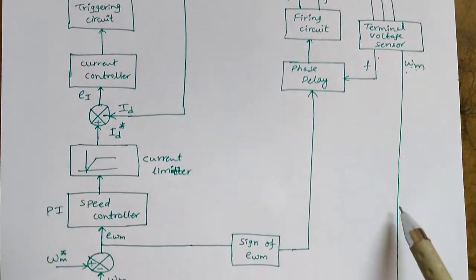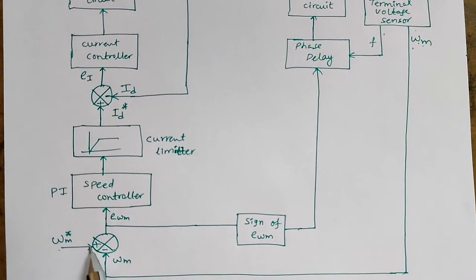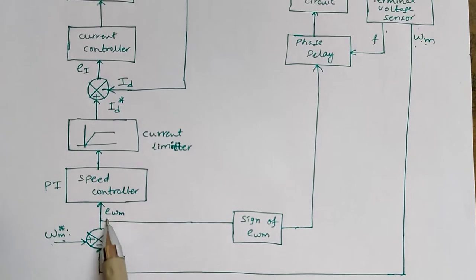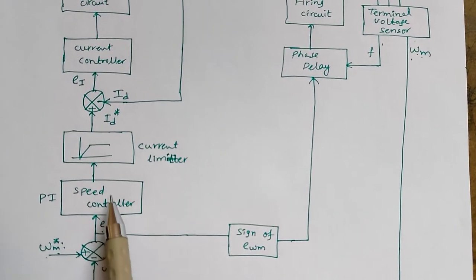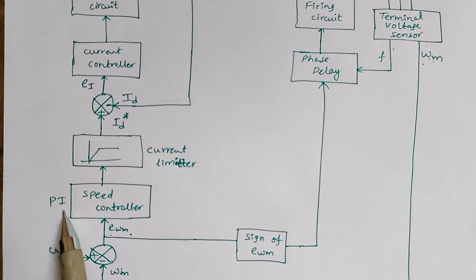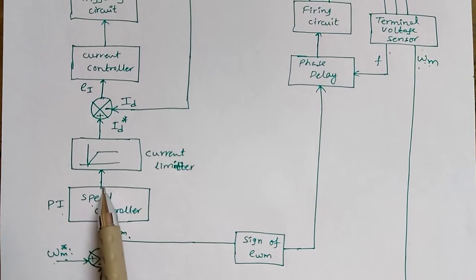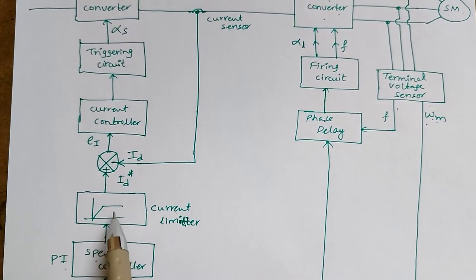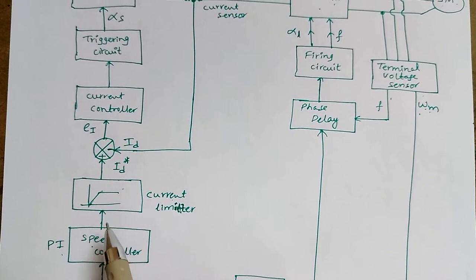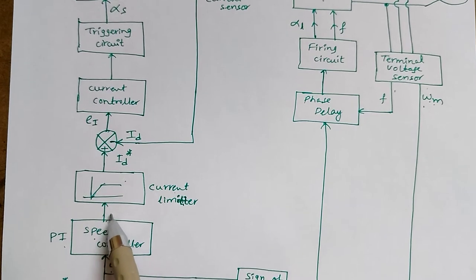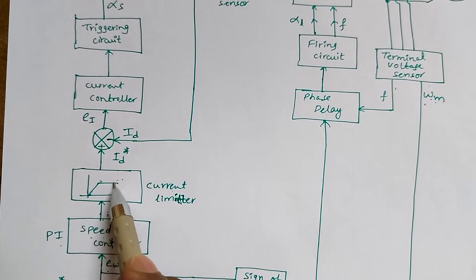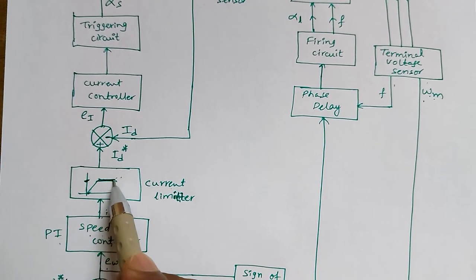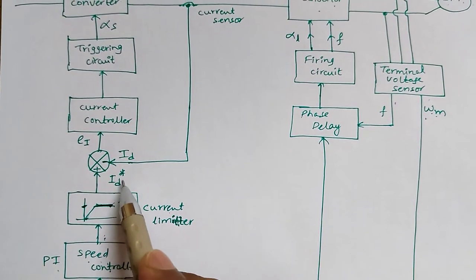The actual speed is compared with the reference speed, and the difference gives the speed error. This error is processed through a speed controller, which may be a PI controller. The PI controller output is connected to a current limiter. Since the converters are rectifiers, they provide only positive current, so only a positive-side current limiter is used. If the output exceeds the maximum limit of the current limiter, it is saturated at that particular value, and that is treated as the reference current.